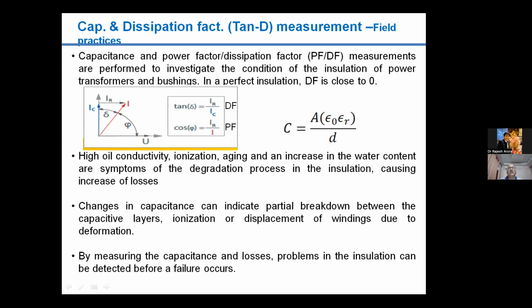But the two factors, if the oil is in good health, or the insulation is good, like that of a new transformer with new oil, both the factors may be equal. Okay. So high oil conductivity, ionization, aging, and an increase in the water content, as I discussed, may cause degradation of the insulation and may cause an increase in the losses of the transformer.